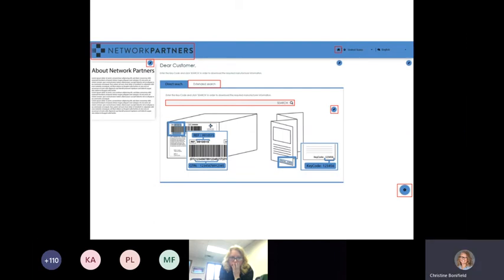After we load the eIFUs and link the SKUs, we will sample a number of random catalog numbers, GTINs, in random languages to confirm that the site is operating as expected. We'll collate all the data that we've loaded, the linking spreadsheets, and the objective evidence of our confirmation test, and attach it to the change order for final approval and closure. The uploaded data and documents can also be exported from the site log as evidence of the change order.